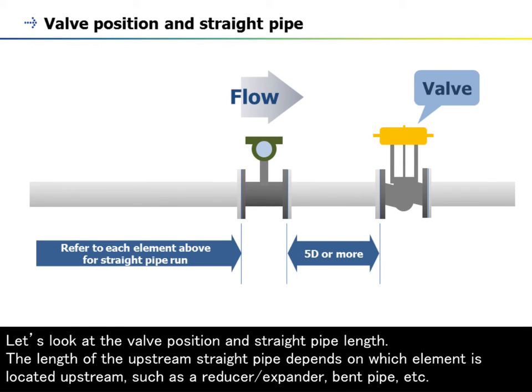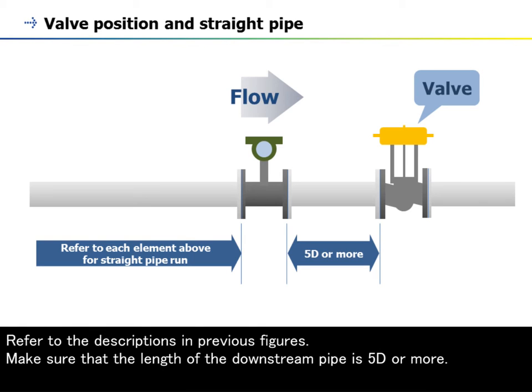Let's look at the valve position and straight pipe length. The length of the upstream straight pipe depends on which element is located upstream, such as a reducer or expander, bend pipe, etc. Refer to the descriptions in previous figures. Make sure that the length of the downstream pipe is 5D or more.